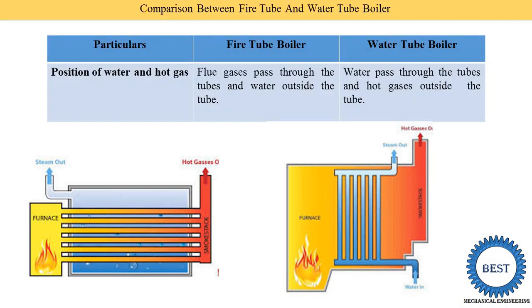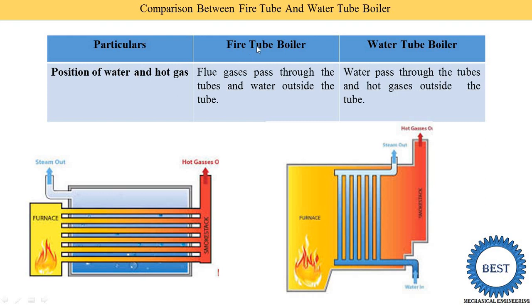The first point is on the basis of positions of water and hot gases. The first column is for particulars, second column is for fire tube, and the third column is for water tubes. So, positions of water and hot gas: here is one boiler — this is the boiler shell, inside this boiler there is a tube and a furnace. Hot gases from the furnace are supplied inside the tube, and water is outside the tube or it is in the shell. This boiler is known as the fire tube boiler — whatever is fire, it is inside the tube. Flue gases pass through the tube and water is outside the tube.